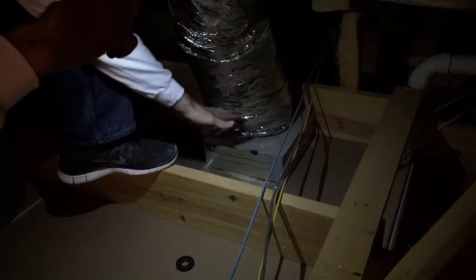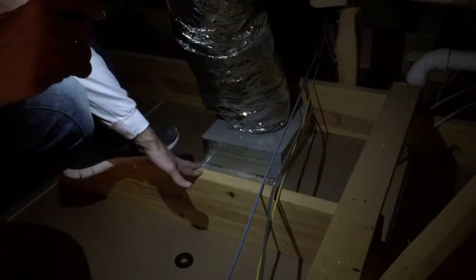Another place where duct leakage can happen is right here at the seam where the supply boot meets the sheetrock. If this isn't properly fastened, sometimes these things can get knocked loose, and then you're blowing air straight into your attic and it's not going into your living space. This can cause all sorts of problems, from air quality issues to just not getting enough airflow in the house, to also allowing a hole from your attic into your house, where obviously the hot humid air is then going to get in and mix with your nice conditioned air.